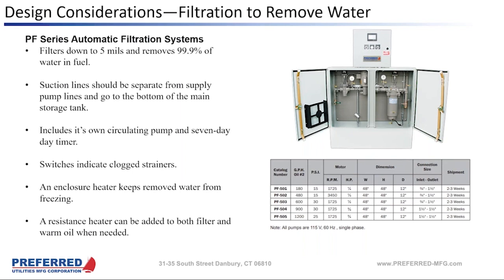Right. I don't know if I've ever had a polisher run too often, but you've seen that, Alex? Yeah, it was a situation where they were running it nearly continuously, and what ended up happening is that the fuel started to show a little bit of premature oxidation. Not the end of the world. Certainly, there was no particulate content, but this isn't something that needs to be run 24/7. This is something that would be run on a schedule, whether it's weekly or whatever, or based on deliveries. But yeah, that is obviously a very extreme case.